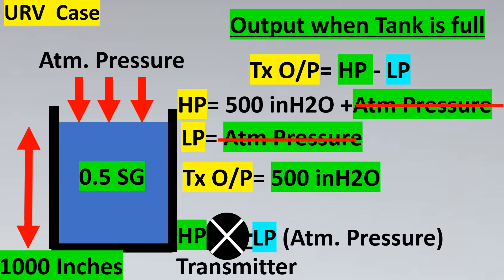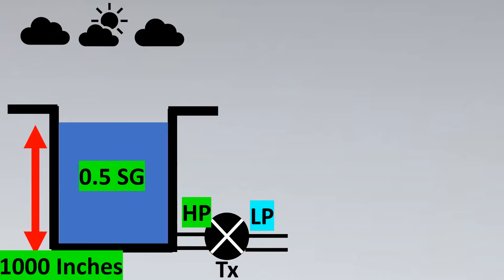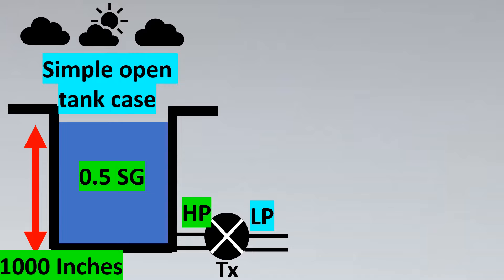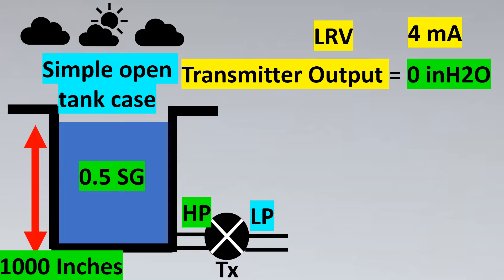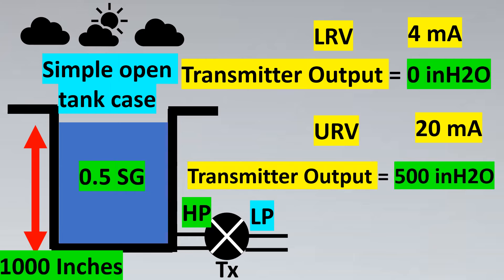Now let's consider cases where the transmitter cannot be placed exactly at the tapping location and must be shifted. First, let's quickly revise the simple open tank case: at LRV (4 mA), the transmitter output is 0 inches of H2O, and at URV (20 mA), the transmitter output is 500 inches of H2O, for the dry leg configuration where the transmitter is exactly at the tapping location.